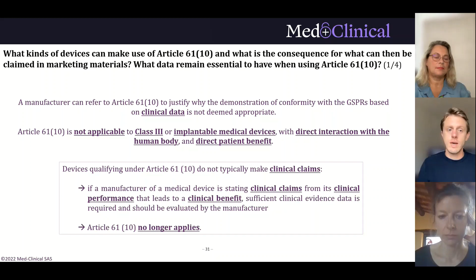So indeed, the manufacturer can refer to Article 61.10 to justify why the demonstration of conformity with the GSPRs based on clinical data is not deemed appropriate. You have to keep in mind that this article is not applicable to any Class 3 device or implantable device or any device with direct interaction with the human body and with a direct patient benefit. So in general, those devices do not typically make any clinical claims, because if the manufacturer of a medical device is stating a clinical claim, which is coming from the clinical performance of this device, which then leads to clinical benefit, you have to prove this clinical benefit by sufficient clinical evidence data. So by this, you cannot use this Article 61.10 anymore.